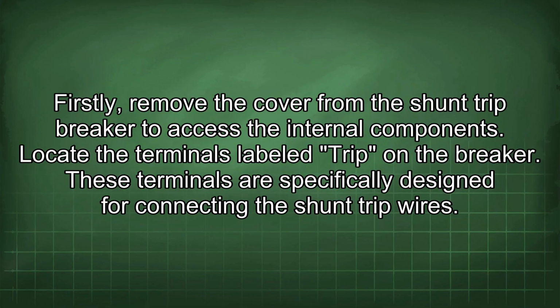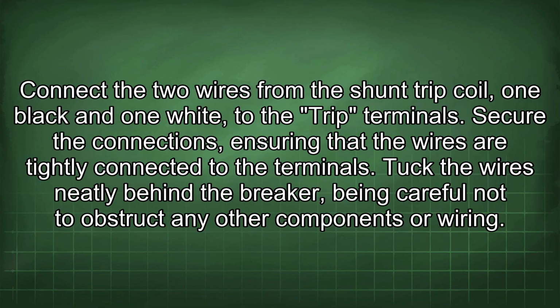Firstly, remove the cover from the shunt trip breaker to access the internal components. Locate the terminals labeled trip on the breaker. These terminals are specifically designed for connecting the shunt trip wires. Connect the two wires from the shunt trip coil, one black and one white, to the trip terminals.